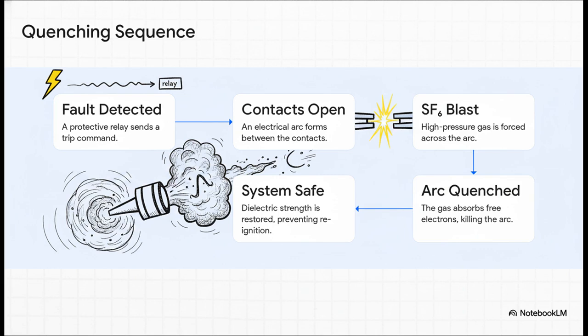First, some kind of fault is detected. A signal goes out. Then, as the mechanical contacts inside the breaker start to pull apart, bam, that arc is born, but instantly, a piston fires a high-pressure puff of SF6 gas right into the arc's path. The gas grabs the electrons, the arc just vanishes, and the gas's insulating property makes sure it can't reignite. The whole thing is over in a tiny fraction of a second.